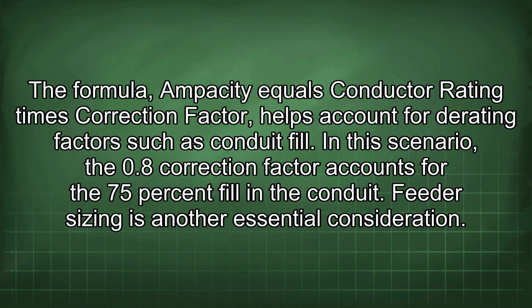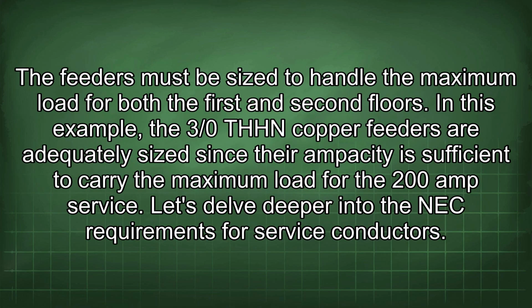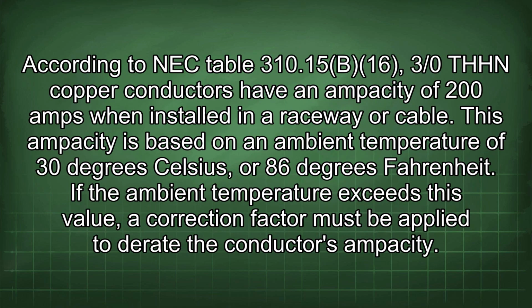Feeder sizing is another essential consideration. The feeders must be sized to handle the maximum load for both the first and second floors. In this example, the 3/0 THHN copper feeders are adequately sized since their ampacity is sufficient to carry the maximum load for the 200 amp service. Let's delve deeper into the NEC requirements for service conductors.